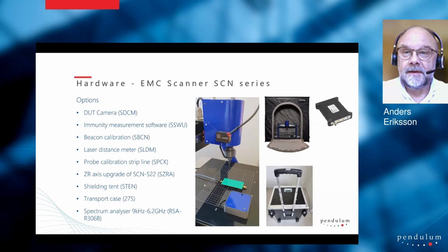Probe calibration strip line. It's this one. It's a strip line board that we use together with a spectrum analyzer with tracking generator, and it allows us to co-calibrate scanner systems, for example, in different parts of the world, where you want to know for sure that both systems measure the same amplitude and frequency.